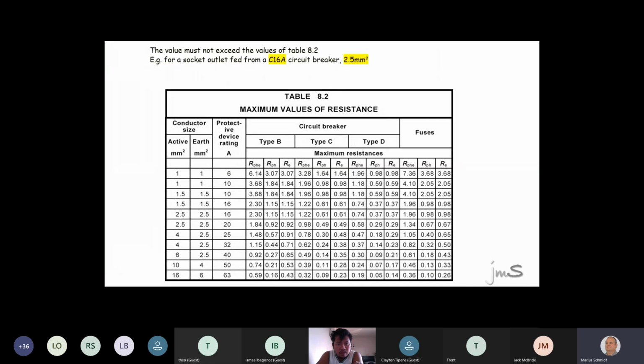Right, here comes the part which is going to suck you up and spit you out, and you won't know what the answer is. Table 8.2 in your 3000 book states the following. From the far left, your active conductor size. The next one, your earth conductor size. The next one, your circuit breaker size. Then, can you see it says B, C, and D? Have you guys ever seen an acronym in front of a circuit breaker? C type, B type, A type. Look at the top question. Can you all see it says C16 breaker? You all agree we're going to look at C.